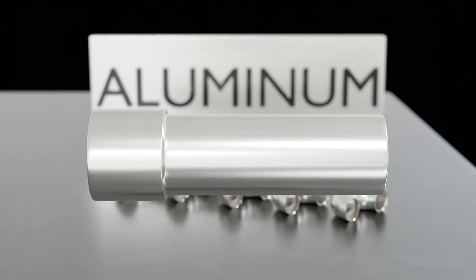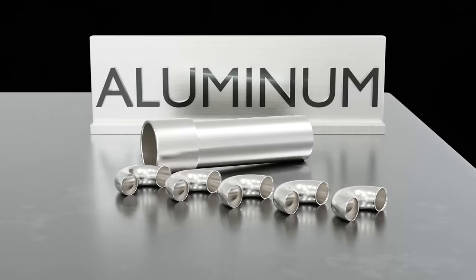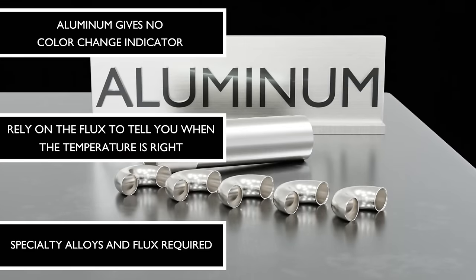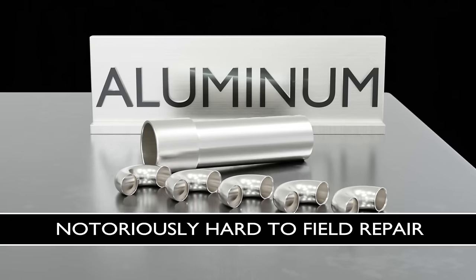And finally, we have aluminum. It's rare that techs will work on aluminum in the field, but it's becoming more common. It has a much lower melting temperature and gives you no visual color indication of target temperature. Generally speaking, you rely on the flux to tell you when the temperature is right. Special alloys and flux are required. You will not use the same alloys and flux that you used for copper, brass, or steel.